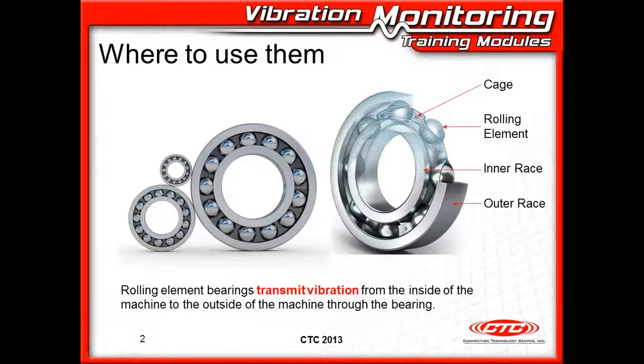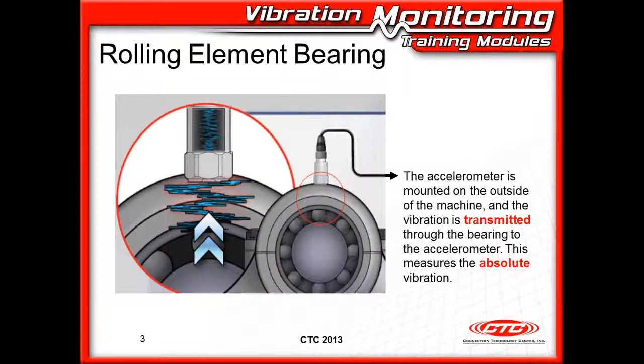Where do we use them? Well, accelerometers are really meant to be used with machines that have rolling element bearings in them. That's because we're measuring the transmitted vibration from inside of the machine to the outside of the machine through the bearing or through the casing of the machine. And as you can see here, we can take this transmitted vibration up into the accelerometer and simply convert it to a voltage, 100 millivolts per G, let's say, and then pass that along to our data acquisition system. And this is a measurement of the absolute vibration of the machine. So we are measuring the absolute vibration with our data acquisition or condition monitoring systems.